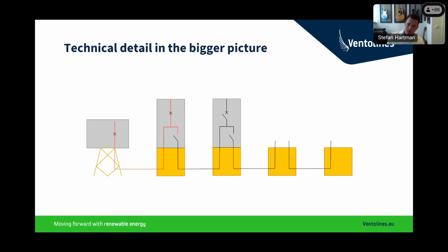So this is a schematic. What we see here on the left is an offshore high voltage substation with an outgoing inter-array cable. We see 4 foundations installed in yellow, and we see 2 turbines installed. The first turbine, the closest to the offshore high voltage substation, is commissioned. It's fully energized and it is in trial run. At this moment, the second turbine is also installed, pre-commissioning is finished, and we would like to energize the turbine and move to hot commissioning. To do that, we need to close the disconnector on the first turbine. Next slide, please. So we want to close this disconnector, and then the string will be energized.